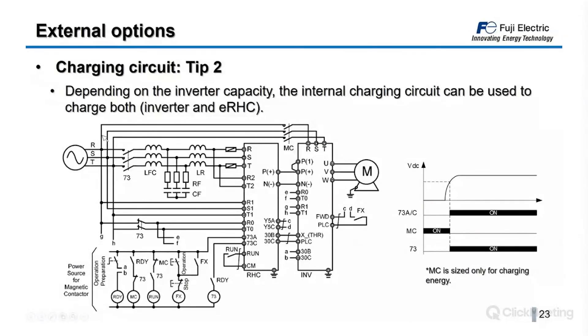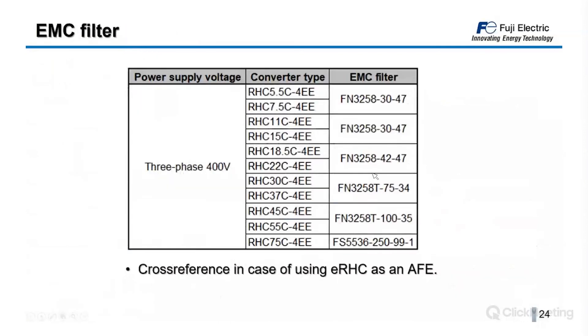For EMC filters, the cross-reference table uses the FN3258 family. Keep in mind: in case the eRHC is working as an active front end (Mode 1), use the reference for the eRHC power; but in Mode 2, the EMC filter must be sized according to the motor and inverter power — not the eRHC power.